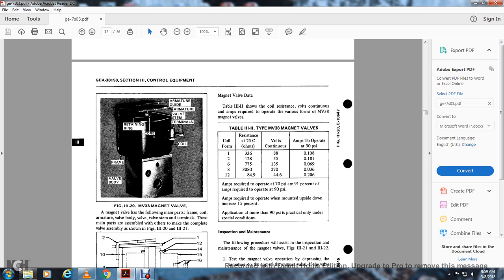Coil form 1: 336 ohms, 88 volts, 108 thousandths of an amp at 90 psi. Coil form 2: 128 ohms, 55 volts, 181 thousandths of an amp at 90 psi. Coil form 6: 775 ohms, 135 volts continuous, 69 thousandths of an amp to operate at 90 psi. Coil form 8: 3080 ohms, 270 volts continuous, 36 thousandths of an amp to operate at 90 psi. Coil form 12: 84.9 ohms, 44.6 volts, and 206 thousandths of an amp at 90 psi.